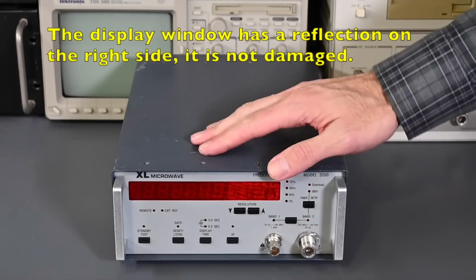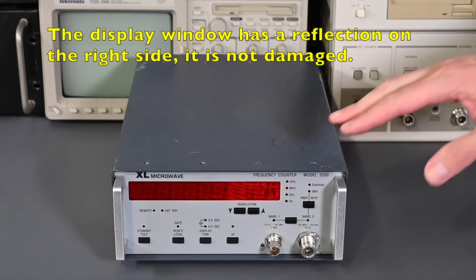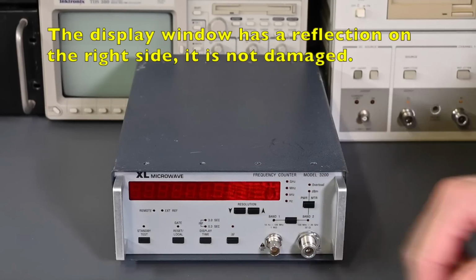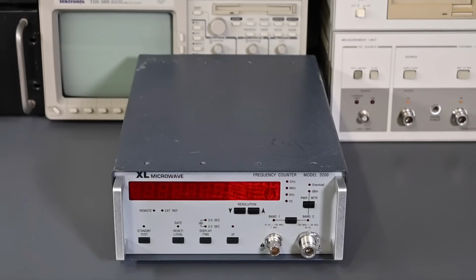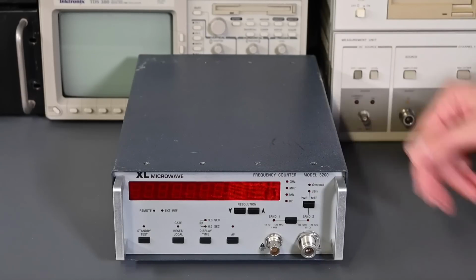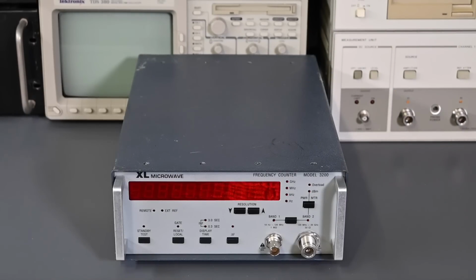So one of the first things that I noticed about the frequency counter is that most of the screws are missing on the top and bottom covers. So there's a place for 40 screws total, 20 on the top cover and 20 on the bottom cover. So someone's definitely been into the instrument previously. I guess they got bored putting the screws back in place because there's only about 4 holding the top cover on and 4 or so holding the bottom cover in place.